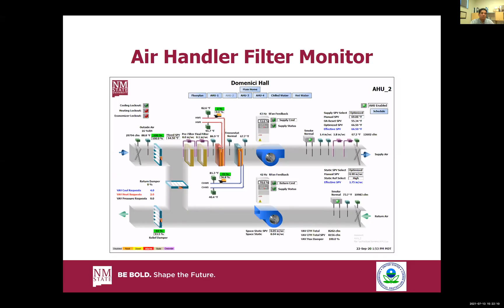So what we've done, we've installed sensors on these filters to determine how much pressure loss or how much restriction there is within that filter. So that way we don't run them beyond their useful life, where we're using excessive fan energy to try to draw through those overly restrictive filters, and we can get maximum use out of them. So we're not replacing them routinely when they don't need to be replaced, but not running them too long where they're so plugged up that it's an energy penalty. So we've actually installed filter pressure drop sensors on our ventilation systems.